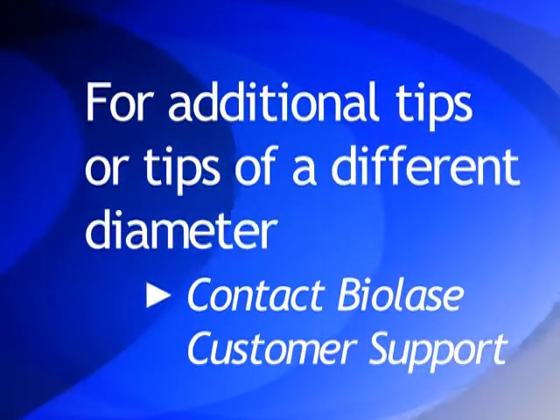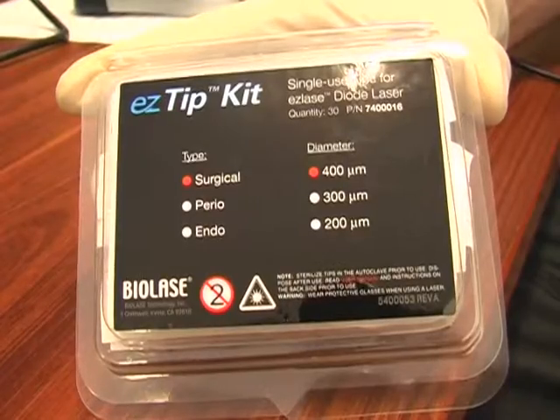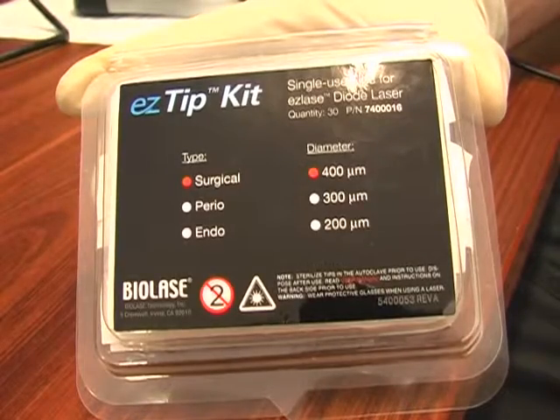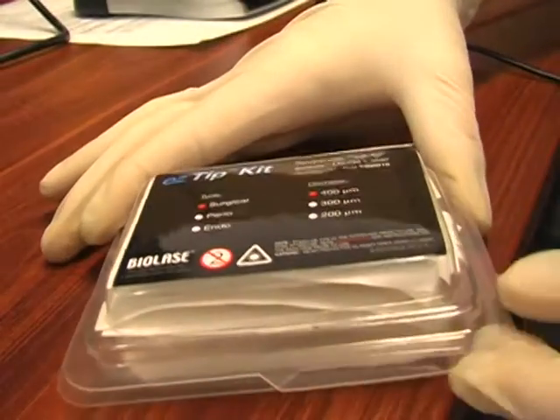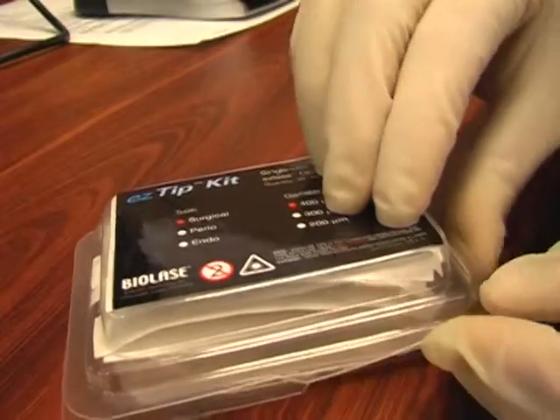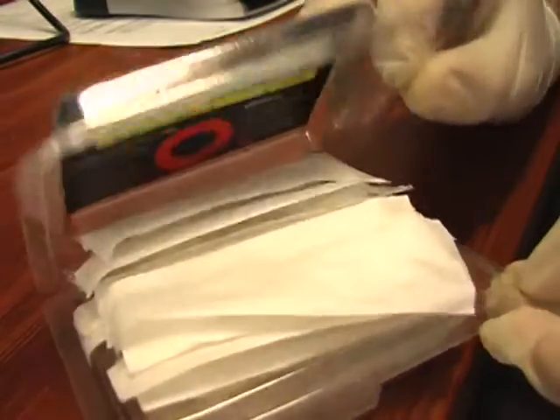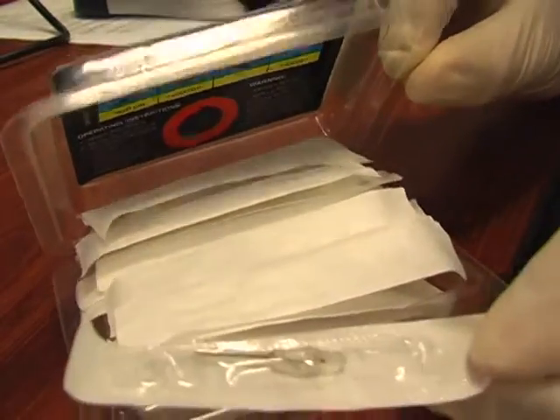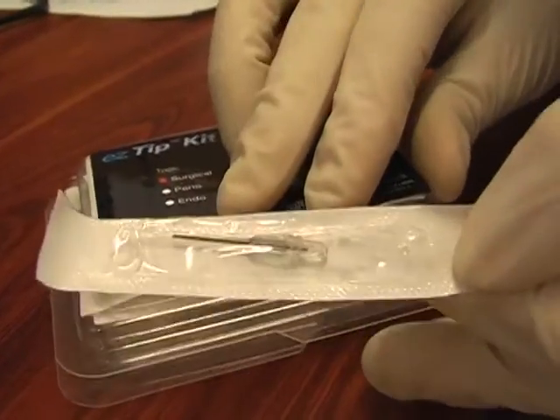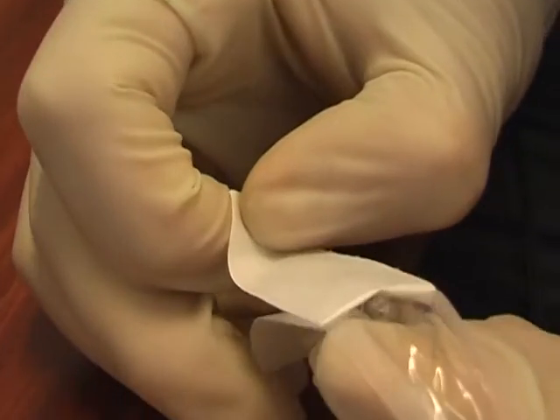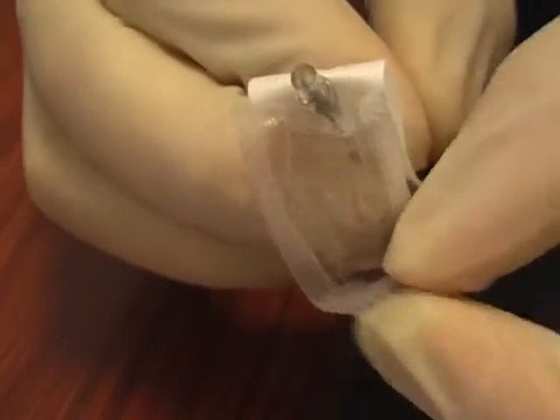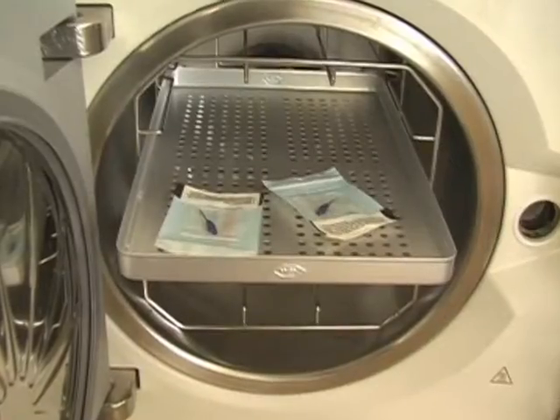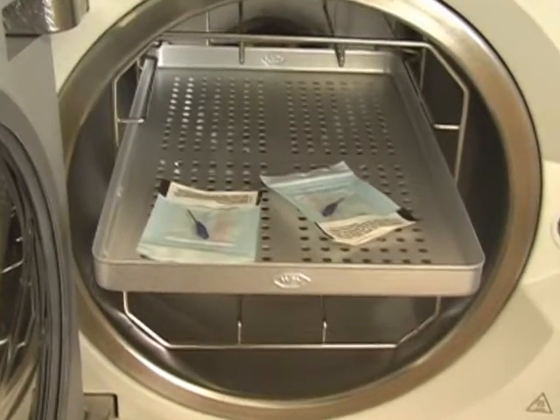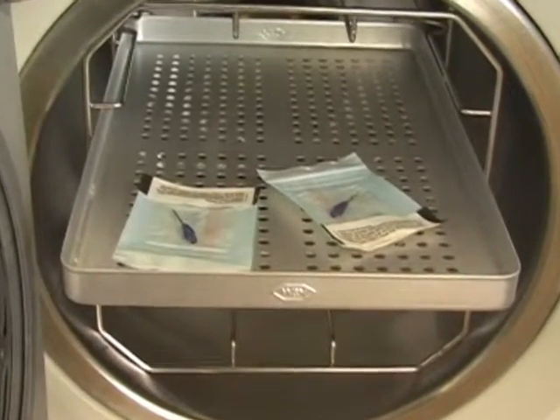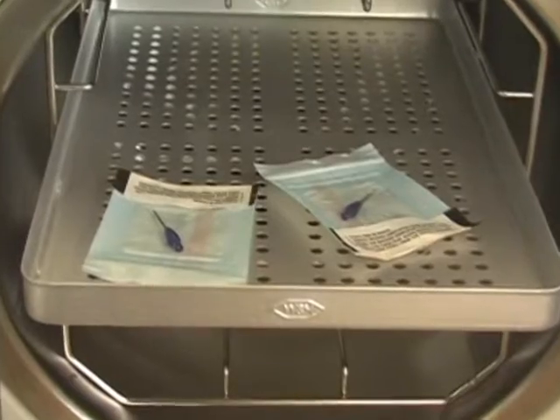An order form is included with your laser. Each tip comes wrapped in an easy to open package. It is designed for a single use and at the end of each procedure should be disposed of in a sharps container. Reuse of the tip could result in the attenuation of laser performance and may cause damage to the fiber or the laser system. The tips as supplied are non-sterile and the packaging is not suitable for autoclaving. Therefore, you should sterilize your tips in an autoclave prior to use. Recommended cleaning and sterilization parameters are noted in the user manual.